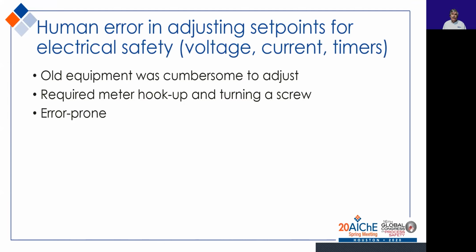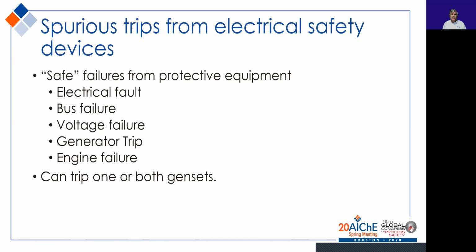We have human error in adjusting the set points for the electrical safety devices: voltage, current, and timers. This is old electromechanical equipment, difficult to adjust; you had to hook a meter up to it and turn a screw, and it was error prone. We have spurious trips from the electrical safety devices. Spurious trips are safe failures from protective equipment that shut the equipment down when it was not supposed to shut down. So it's a fake trip, if you will, for electrical faults, bus failures, voltage failures, generator trips, engine failures, and it can trip one or both gensets.